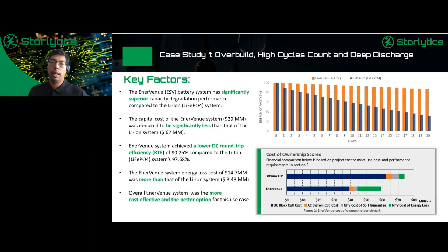So the outcome of that is for a 100 megawatt hour project, 2.1 cycles daily, we needed about 112 megawatt hour at the beginning for the EnerVenue system at year 0. But for lithium, we needed around 219 or 220 megawatt hour. So that's the scale of difference we're talking about.